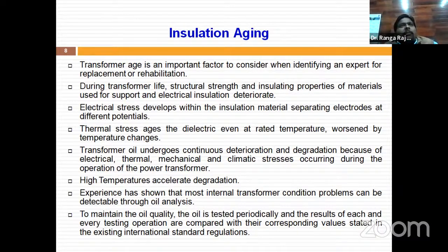Now we will focus on aging. Transformer age is an important factor when identifying the need for replacement or rehabilitation. During a transformer's life, the structural strength and insulating properties of the materials used for support and electrical insulation degrade. A transformer is generally designed for 50 to 60 years of age, but due to various operating conditions and faults in the system, these degrade the performance of the insulation - that is aging.